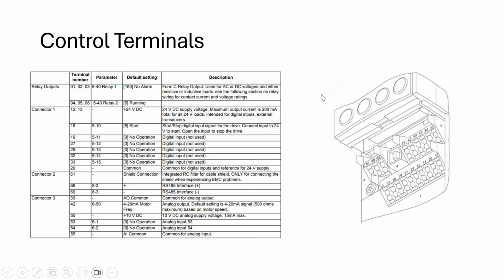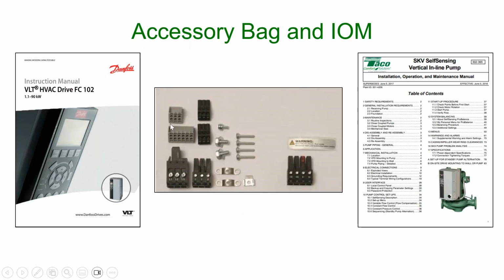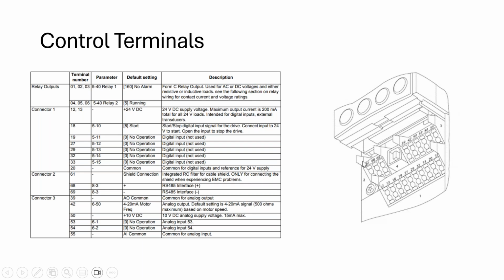And here's the control terminals all broken out. And I'm not going to go through them all here, but you can see they're all numbered inside of one of these pieces right here, right? And then there they are all listed up here. And that's where you start wiring to the drive. Depends on how you want to set it up or whatnot, or accept some external signals, or to read to the BMS system. So you can do that as well. And then there's actually some potential for parallel pumping, for alternating pumping. So let's say you had 2 pumps and you want to alternate them, right? You have a backup, or 3 pumps and you want to alternate them. So you can do that as well. But you'll see some of those photos as we go through this as well.